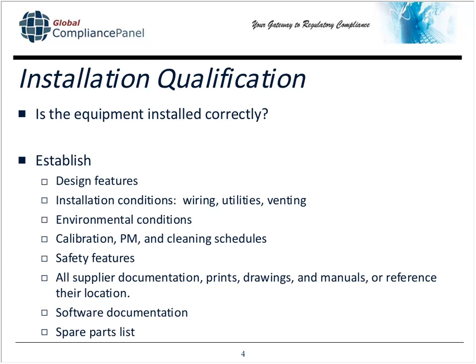I mentioned a sealing machine a few moments ago. This is a machine that's used to seal pouches. Well, this piece of equipment is more than likely going to be used in a controlled environment, or even more so a clean room. In these cases, you need to make sure that this piece of equipment can be used in such a controlled environment or clean room. If you have a piece of equipment that gives out exhaust, you can't use that in a clean room, which renders this piece of equipment unable to be used in that location. You also want to establish calibration, preventive maintenance, and cleaning schedules.